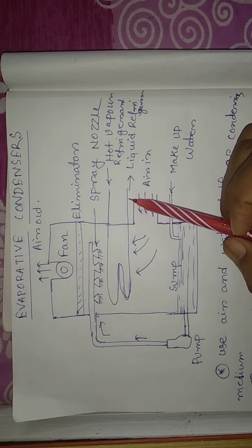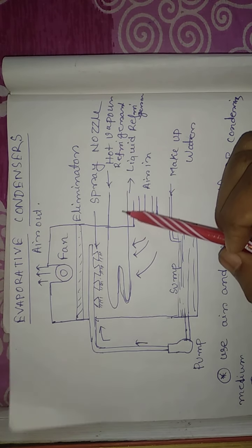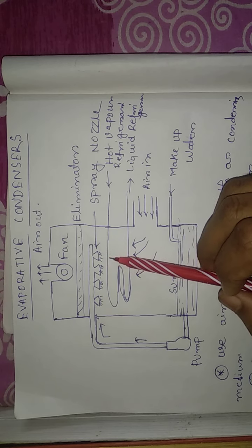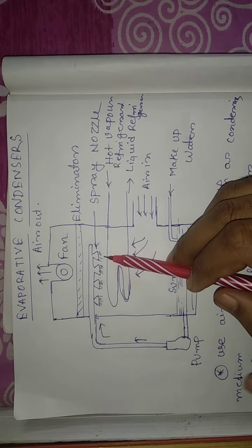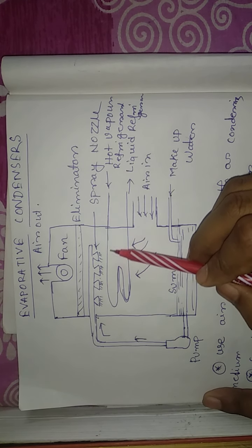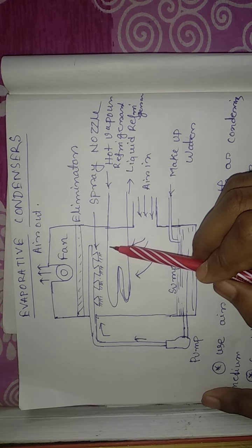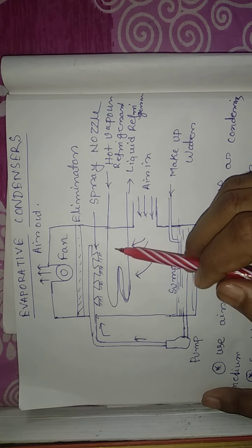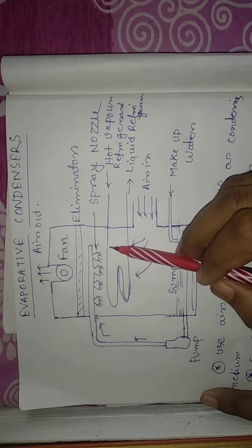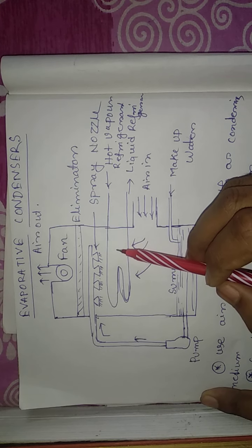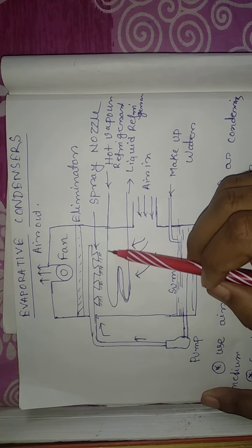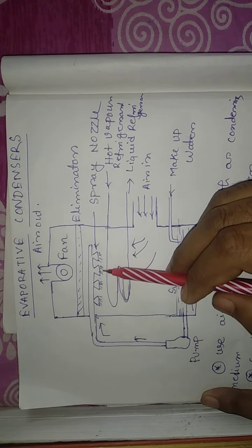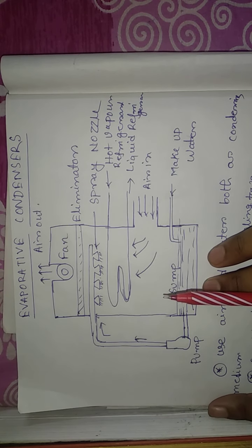But the heat transfer from the refrigerant, because as it contacts the spray water on the condenser coil, the heat transfer takes place from the refrigerant through the condensing tube walls and into the water. That is a wetted surface, actually, the outside surface of the tube.